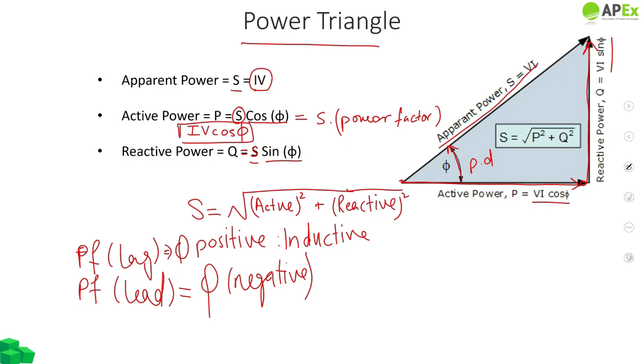While when the power factor leads, phi would be negative, and this load is going to be capacitive, as discussed in the previous slides. So in case phi is positive, our reactive power would be facing north, just like this triangle. However, when our power factor is leading, or when there is more capacitor element in the circuit, our reactive power would be facing south like this, and the apparent power would be given like this.